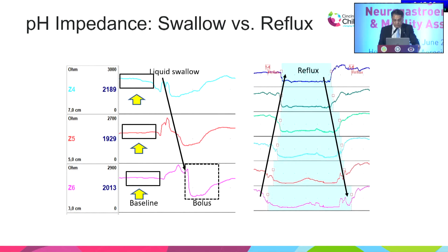So the software is adjusted to the point where if the impedance drops below 50%, only then will the software call it a reflux. So what if it drops only 49%? The software will not call it a reflux event. So therefore, you really have to manually go through each and every episode and see if it is truly a reflux or if there were some missed reflux events. The right is a true reflux event where the impedance drops to below 50% from below upwards, and it's a full column reflux going from bottom to the proximal esophagus.